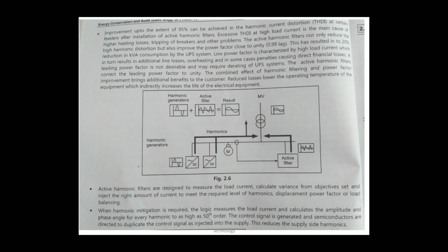A leading power factor is not desirable and may require derating of the UPS system. The active harmonic filters correct the leading power factor to unity. The combined effect of harmonic filtering and power factor improvement brings additional benefits to the customer: reduced losses and lower operating temperature of the equipment, which indirectly increases the life of the electrical equipment.